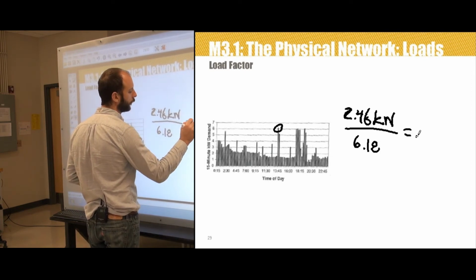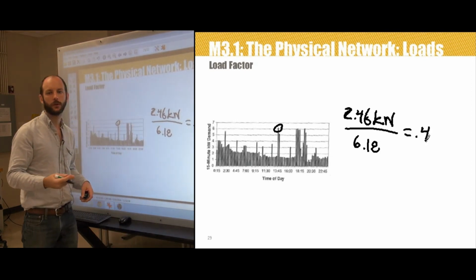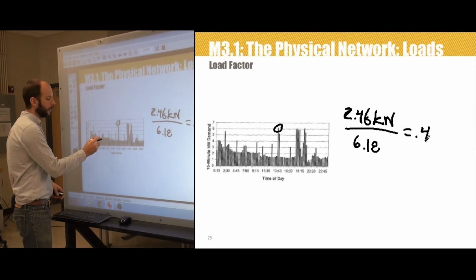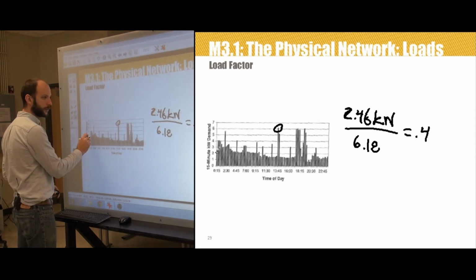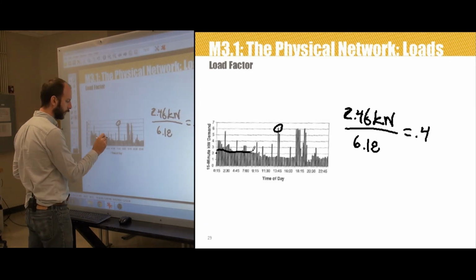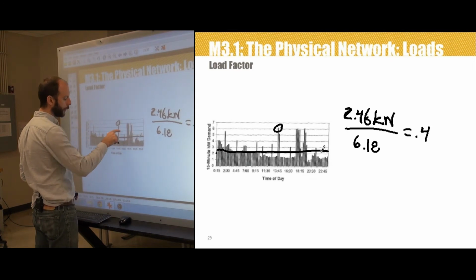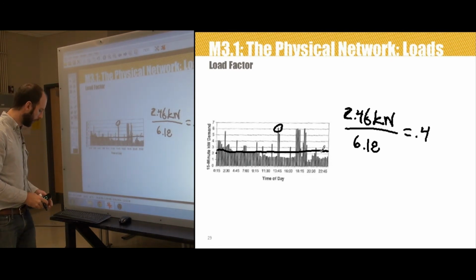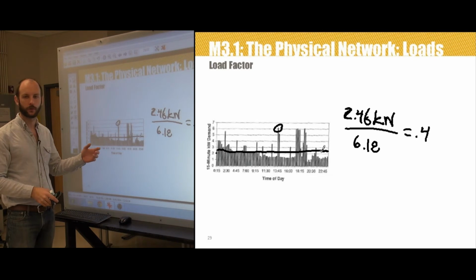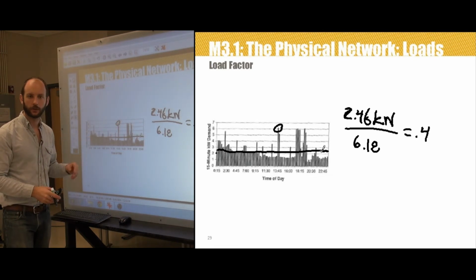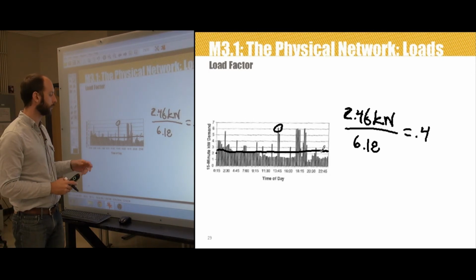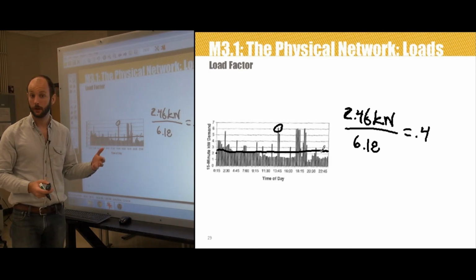And we get a load factor of 0.4 for this. Not a great load factor. We can see that the average electricity consumption for this person is about right there. And there are some pretty big excursions, which means all the money that was spent for transformers and everything to supply that 6.18 wasn't getting utilized. It was a capital expense that wasn't making the electric utility much money.